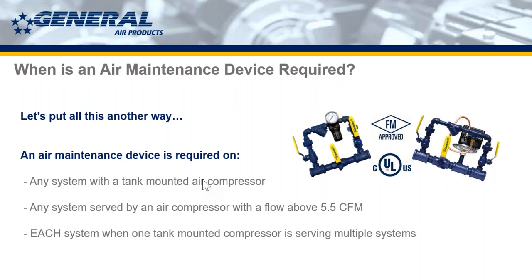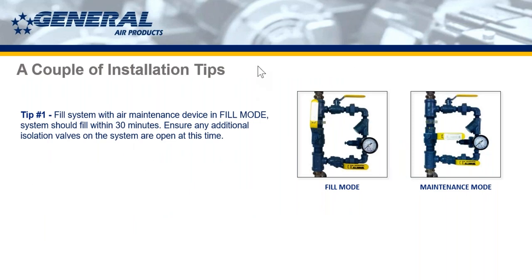Each system, when one tank-mounted compressor is serving multiple systems. So again, you need an air maintenance device on each riser that a compressor is hooked up to, not just the one compressor. Couple tips here. I think I mentioned this before, but again, make sure you fill your system with your air maintenance device in fill mode, and you can see the orientation there for fill mode. And ensure any additional isolation valves on the system are open. So you want the full flow of the air compressor when you're getting your 30-minute fill. And after that, we want to regulate it down. So you fill it up to 40 PSI in 30 minutes as fast as possible.